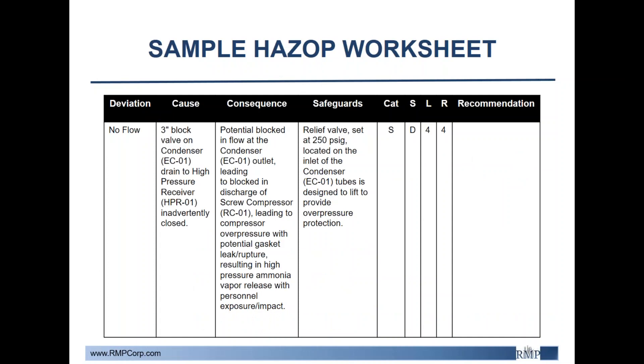Here is a sample HAZOP worksheet to give a better idea of what is involved in the overall HAZOP process. To develop a cause, first select the deviation being discussed — in this case, no flow — and then develop your cause. Once the cause is established, the team discusses the ultimate consequence without crediting any safeguards and ranks the severity. The team then addresses safeguards, discusses likelihood, and gives the scenario an overall ranking. If the ranking is outside acceptable industry scope, recommendations should be made to eliminate the risk.